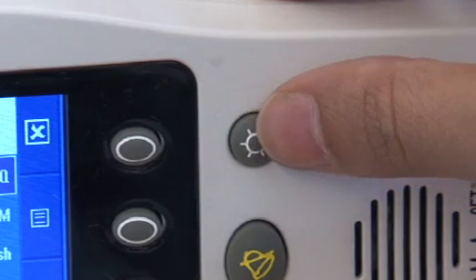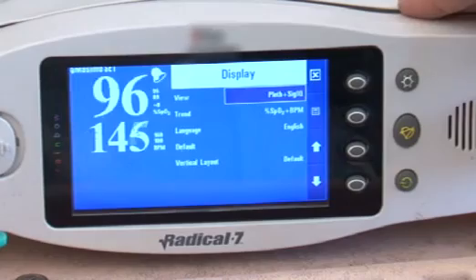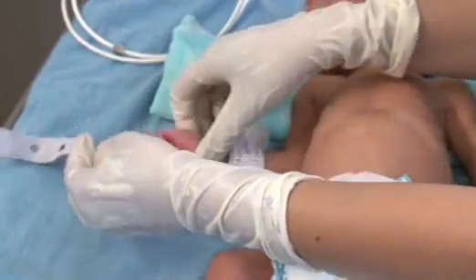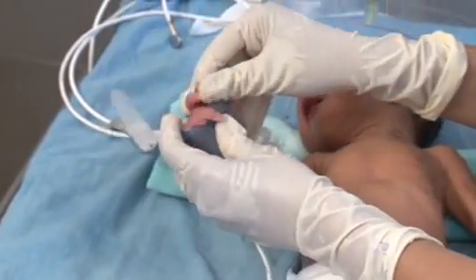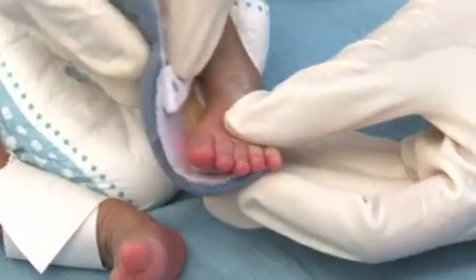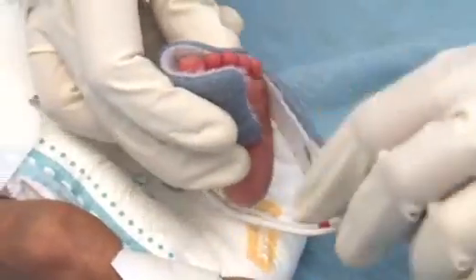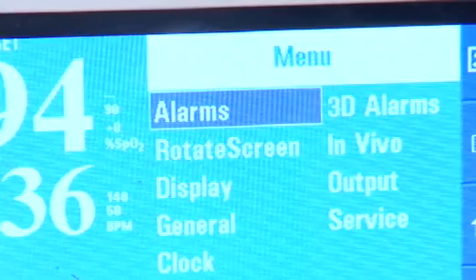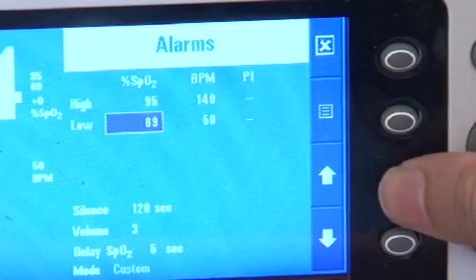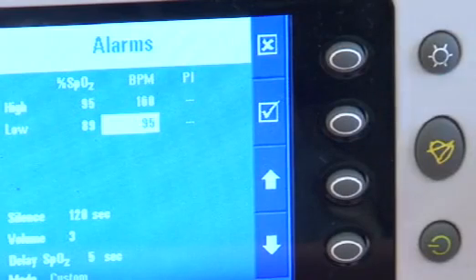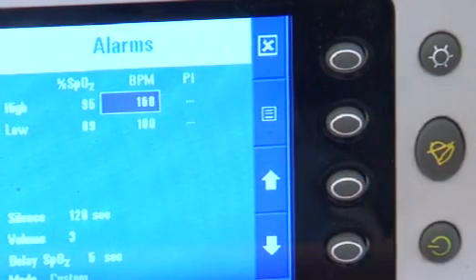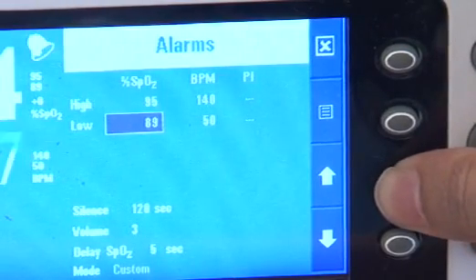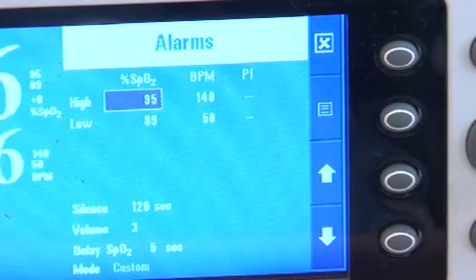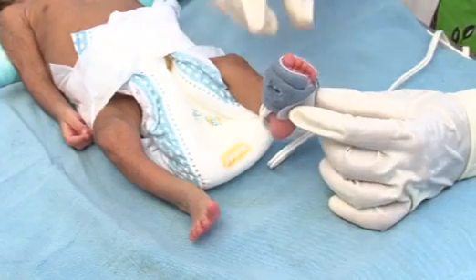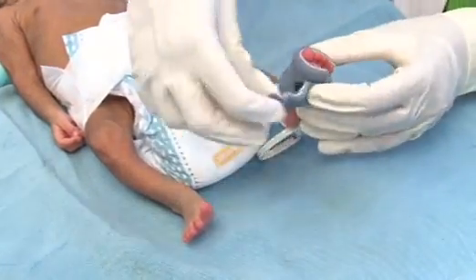Key points. Familiarize yourself well with the display panel and controls. Ensure that the probe is touching the skin and away from direct light. Make sure that both sides of the probe are directly opposite each other. Set the pulse oximeter alarms for high and low oxygen saturation, 89 to 95% oxygenation and the newborn's heart rate at 100 to 160 beats per minute. Titrate oxygen delivery to keep saturation between 90 to 94%. Change the site where the probe is attached once every shift or after every 8 hours. Do regular maintenance and ANC.